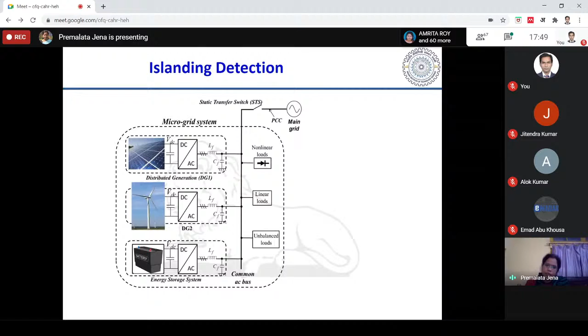So in our research, what we thought of is to have a central microgrid control station, from where we monitor the lines - a simple network I've shown in front of you. From these breakers - this is the breaker of my SBDR, meaning synchronous based distributed energy resource, and IBDR meaning inverter based distribution resource - they have their own breaker through which they are connected to the main grid, to the microgrid.